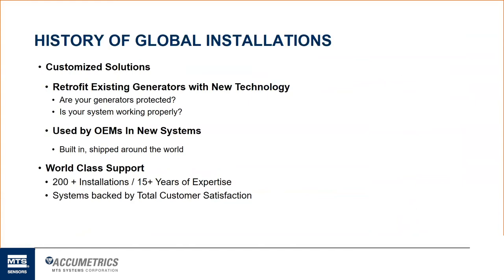So a little bit of history of our global installations. Again, we offer a customized solution. So we are targeting more of a retrofit market where there are those existing ground detectors installed on these brushless exciters, and the customers have those customer pains. They have those issues with them. It's a newer technology. It's a much more precision measurement. It allows the customer to have more confidence that their machine is being protected and being monitored.